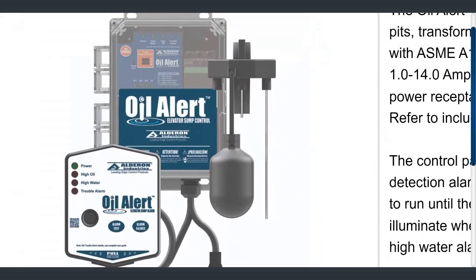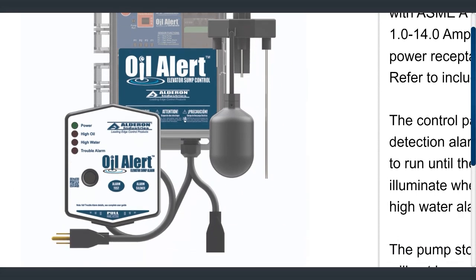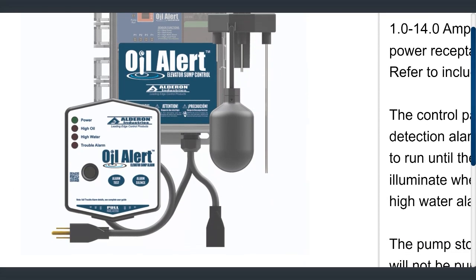And then it has a preset oil and water sensor there. So it has 3 probes. The bottom probe, once the liquid comes up, is just kind of telling, that's the off probe. So the liquid would keep rising. If something conductive like water touches the second probe, that would turn your pump on to pump out any water you have in your system. And if it keeps rising and hits a third probe, you get your high water alarm. If it keeps going up and the float comes up, that's your high oil alert.